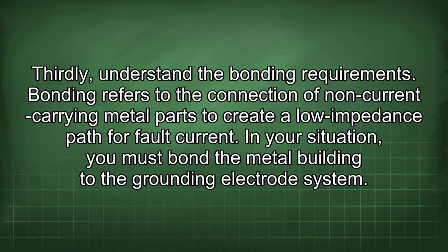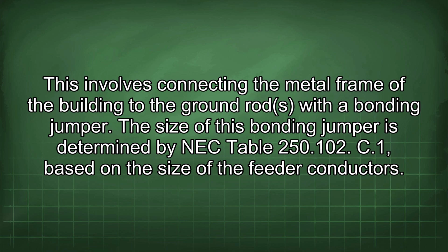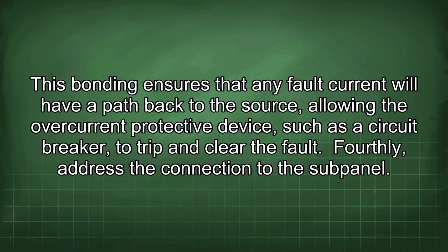Thirdly, understand the bonding requirements. Bonding refers to the connection of non-current carrying metal parts to create a low impedance path for fault current. In your situation, you must bond the metal building to the grounding electrode system. This involves connecting the metal frame of the building to the ground rods with a bonding jumper. The size of this bonding jumper is determined by NEC Table 250.102 C1, based on the size of the feeder conductors. This bonding ensures that any fault current will have a path back to the source, allowing the overcurrent protective device, such as the circuit breaker, to trip and clear the fault.